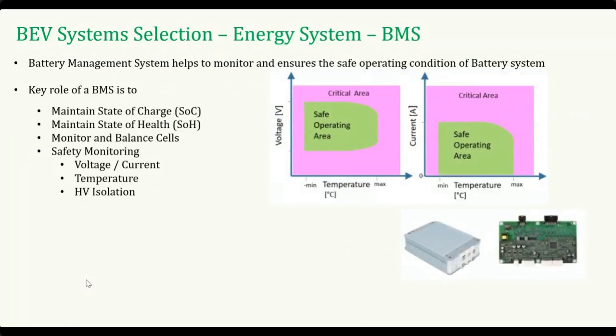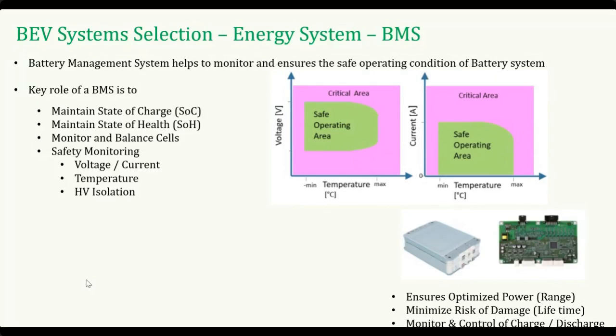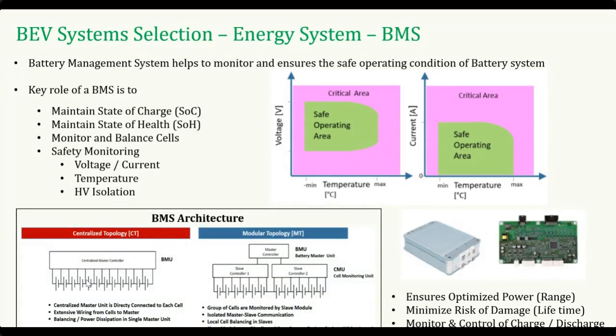Next is the battery management system. The BMS acts as the control system for the batteries, helping to monitor safe operating conditions. As you can see from the architecture, it can be a single circuit which monitors and controls the whole battery system, or a master-slave arrangement to control and evaluate parameters related to state of health, state of charge, cell balancing, and safety monitoring of voltage, current, temperature, high voltage isolation, and many other functions.